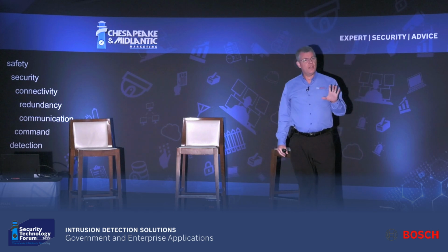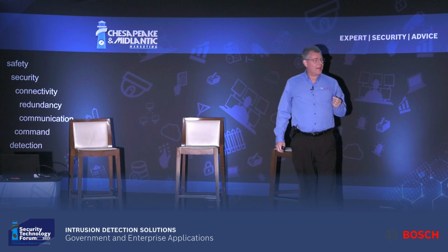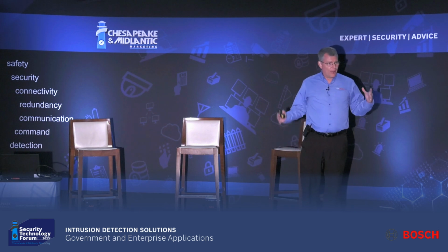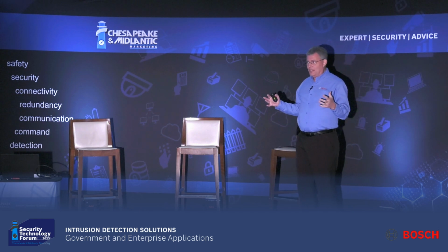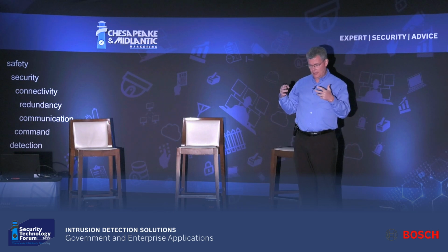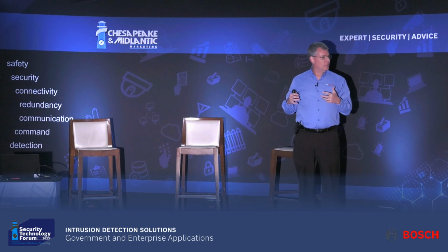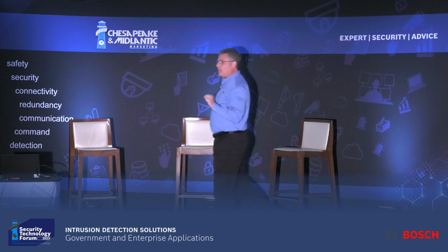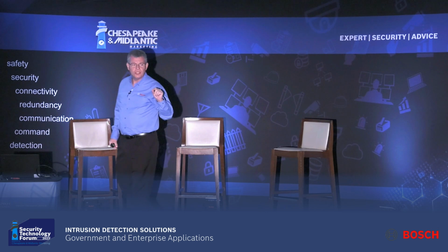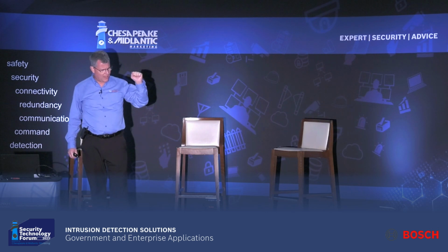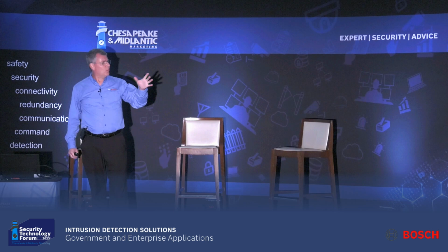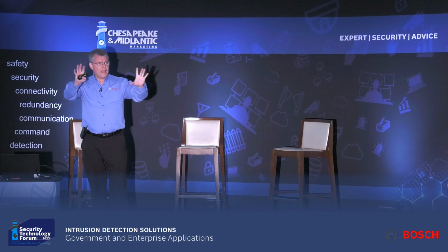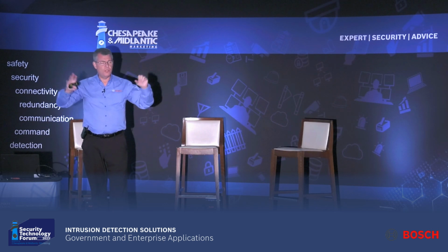Motion detectors, and it's funny, if you read through the requirements of UL 2050, it doesn't even really say that about the intrusion panel. The brains, the thing that runs this whole thing, you read through there and it really doesn't say anything about UL. But, dude, put a UL listed panel in there. They do say UL listed commercial motion detectors that they need to meet. I think it's 639, the requirement for motion detectors. So you need to have a UL listed commercial product to put it in a SCIF.